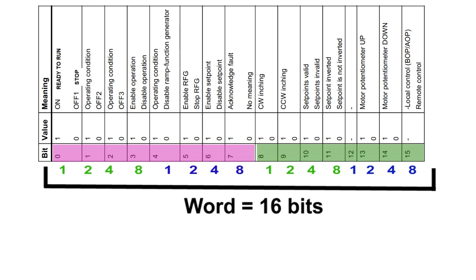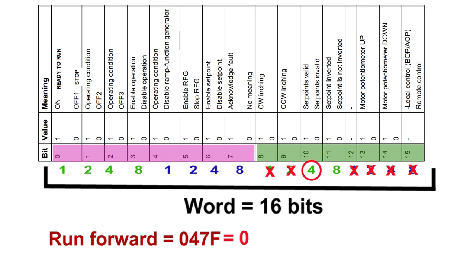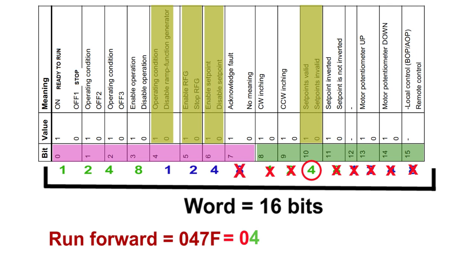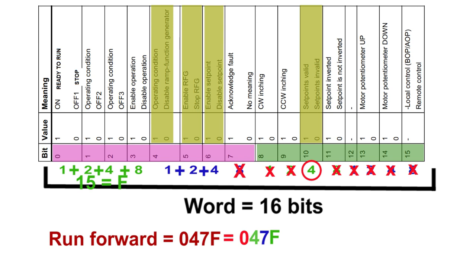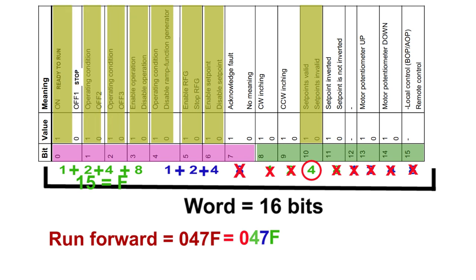How is the code 047F created? The last four bits are not used, so it equals 0 — that 0 comes at the first place. From the next 4 bits, we use bit number 10, whose value is 4 — so 4 comes at the second place. From the next 4 bits, we use bits 4, 5, and 6; adding those values gives 7 — so 7 comes at the third place. From the last 4 bits, all four are on, giving a sum of 15, which in hexadecimal is F. So the code is 047F. Sending this to the control word via Profibus starts the motor in the forward direction.